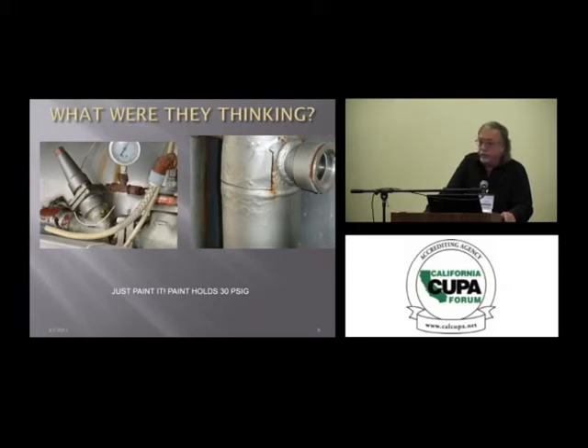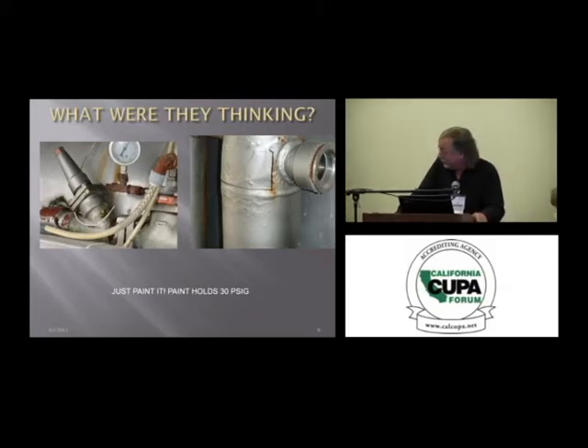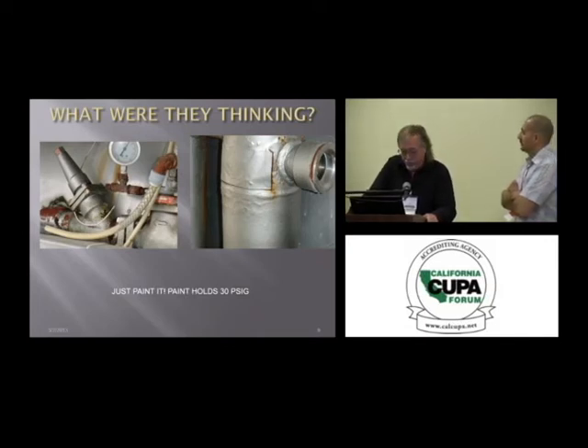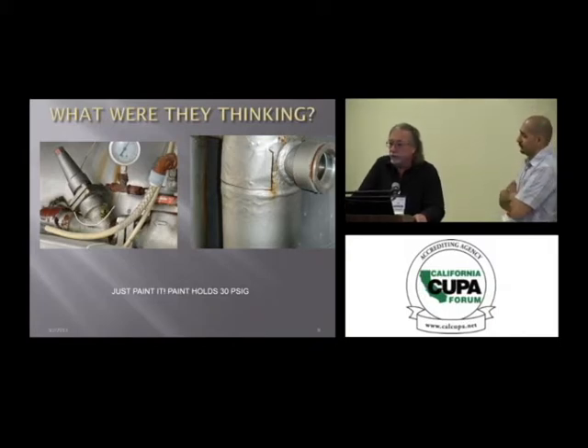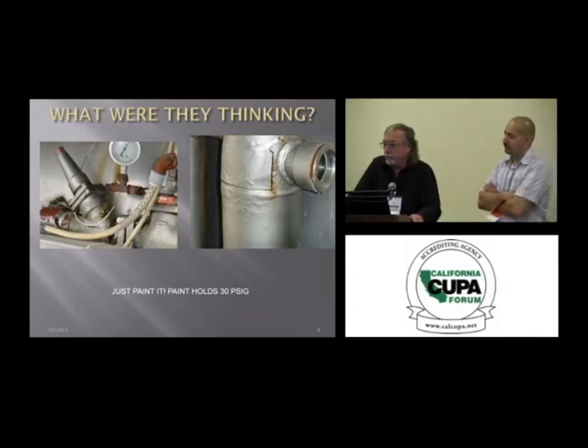Yeah, you're going to see a lot of pictures on piping, bad valves, and hopefully they'll get taken care of shortly here. But one of our most common failures, what we see out there that causes most problems, is corrosion on piping and valves, especially under insulation, where the vapor barrier has been degraded, moisture and air has gotten to that pipe, and then the corrosion starts. Every facility should have a corrosion prevention program. And that's basically random inspections every month, removing small areas of insulation where you see moisture or frost or rust coming through, etc.